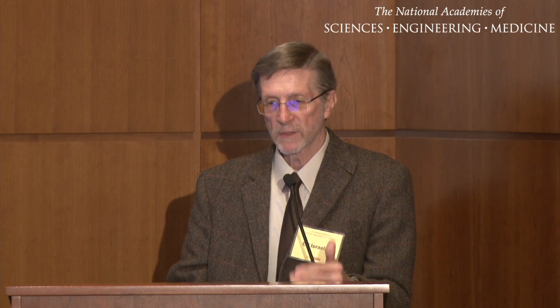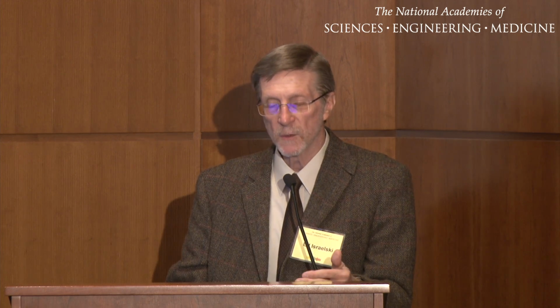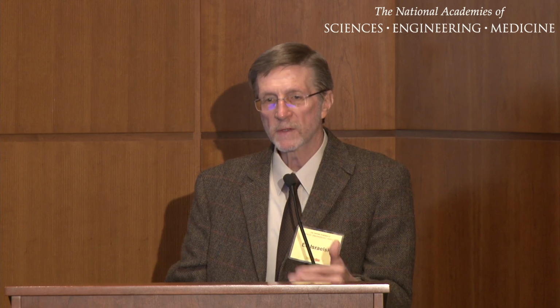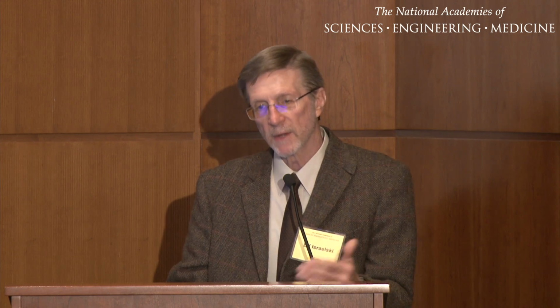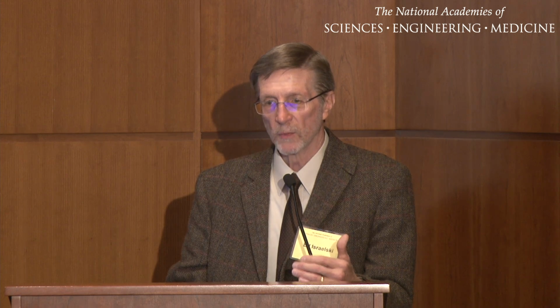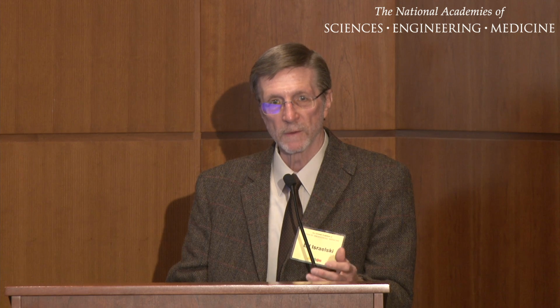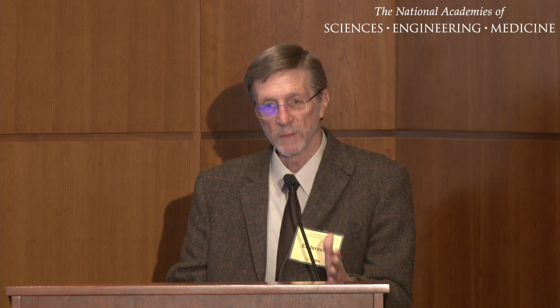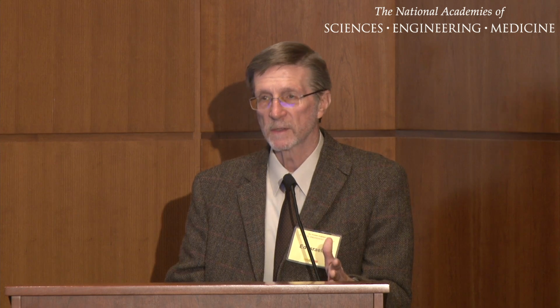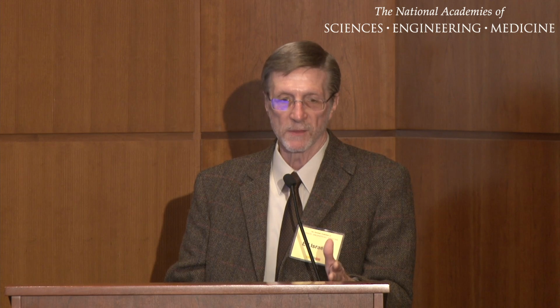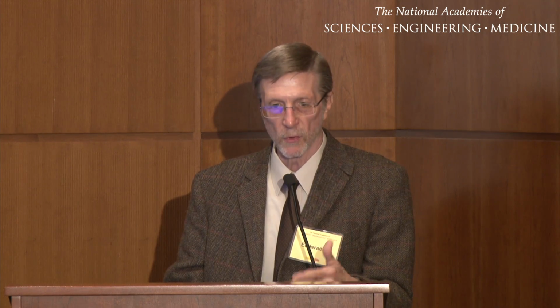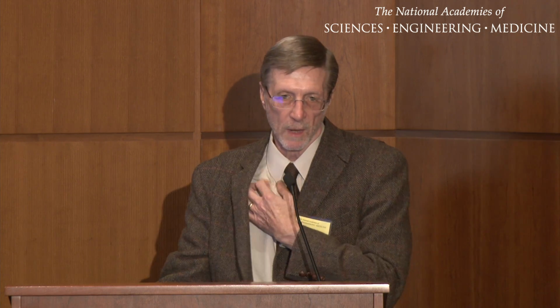So you look at formally and systematically each and every task, what could go wrong, what are the consequences, the harms that could result, and then you prioritize your design work based on that. And later, when you do some validation testing, you'll use this risk analysis to pick out the most critical tasks that you need to be sure are tested, to be sure that improvements, mitigations that you've made, in fact, work. And these are all iterative. I've simplified this diagram by taking out a lot of the feedback loops. This risk management gets done early and then repeated as you learn more as the design unfolds from its early prototype stages to be farther advanced.